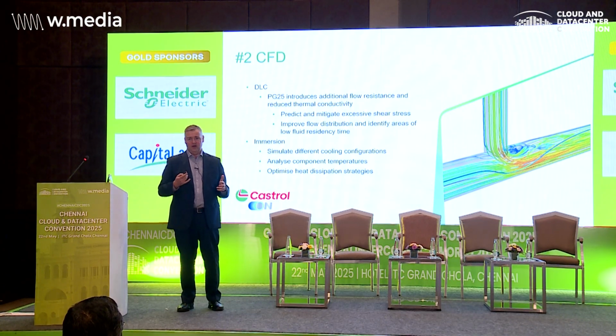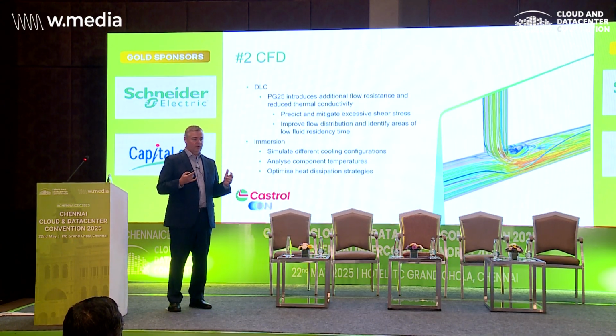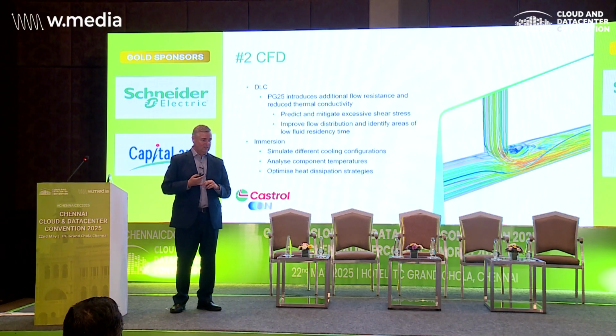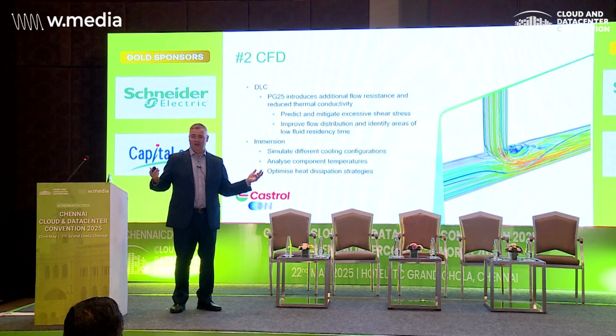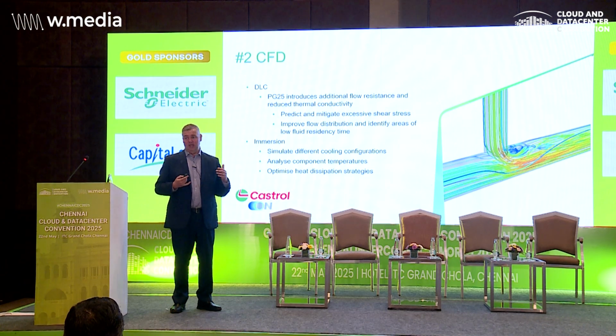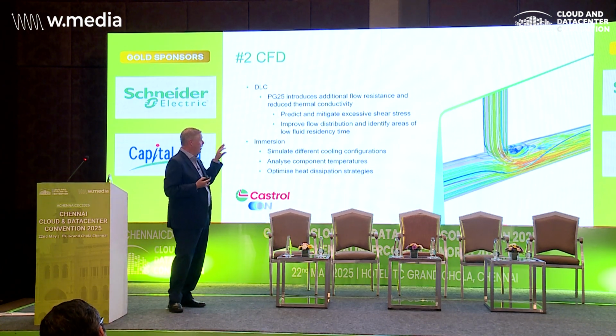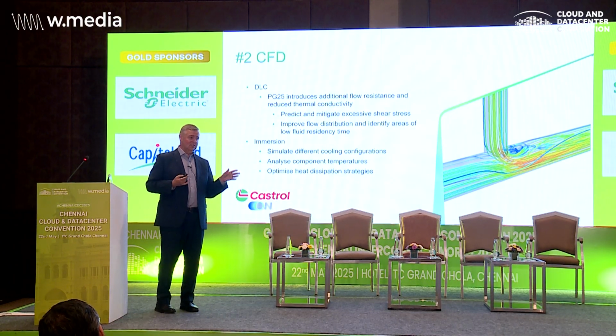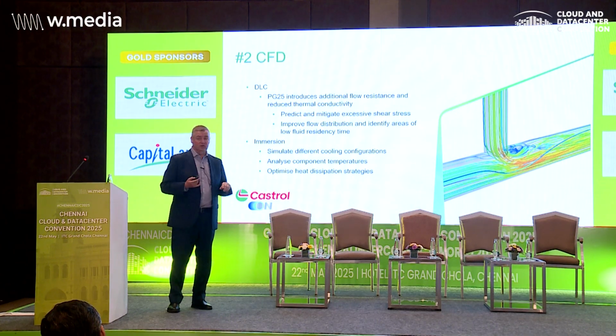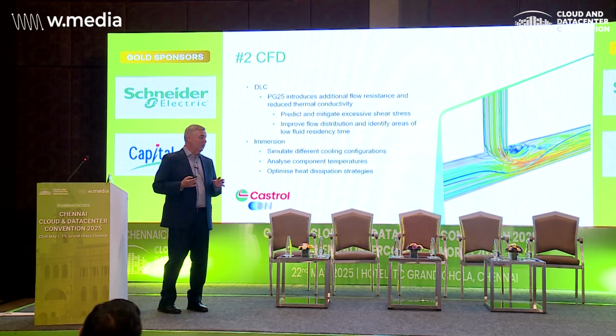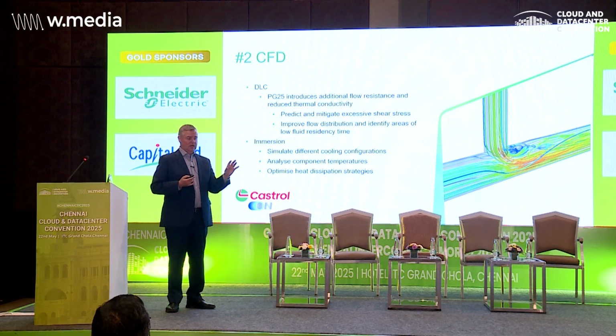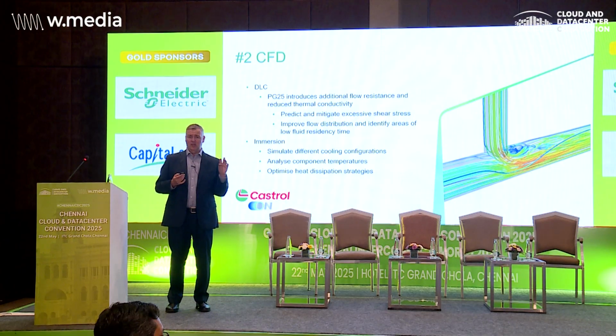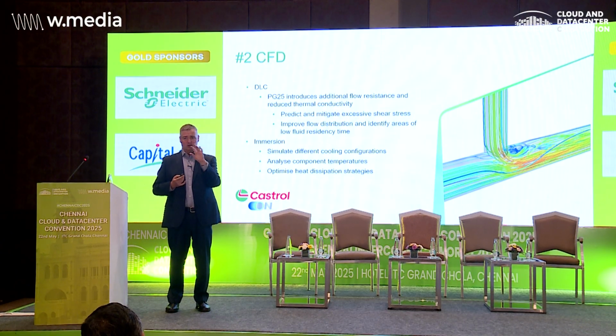Simple things like pipework and the interaction of the fluids with pipework. Some of the work we've been doing in our labs and with different parts of the ecosystem - we always know CFD from air in data centers, but now we're actually using it to mitigate risk with fluids as well. With DLC, when we introduce a water-based coolant into the system, we're going to increase the flow resistance and reduce the thermal conductivity. Now, what that means is that using CFD tools, we can model the thermal and mechanical stresses that the pipework and the cold plates, the CDUs, come under at different stages, and we can predict and mitigate those losses.